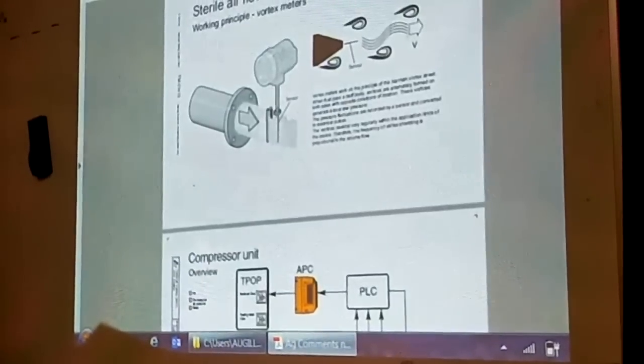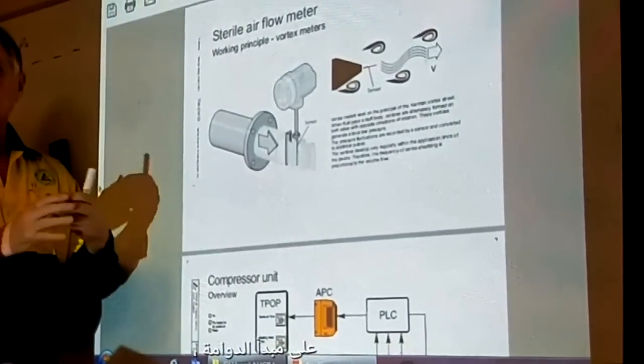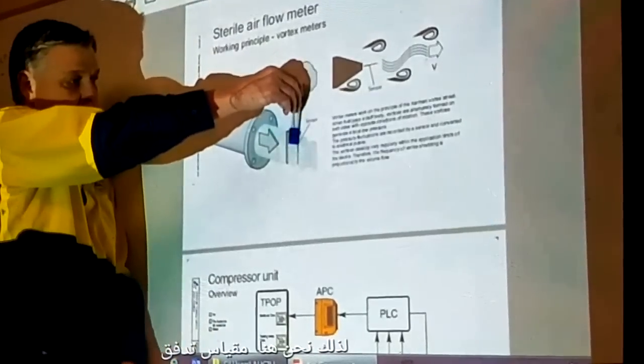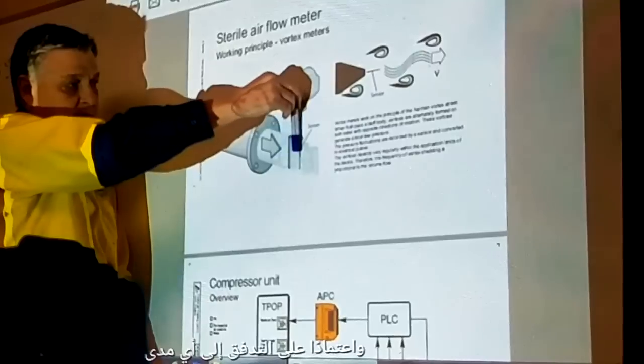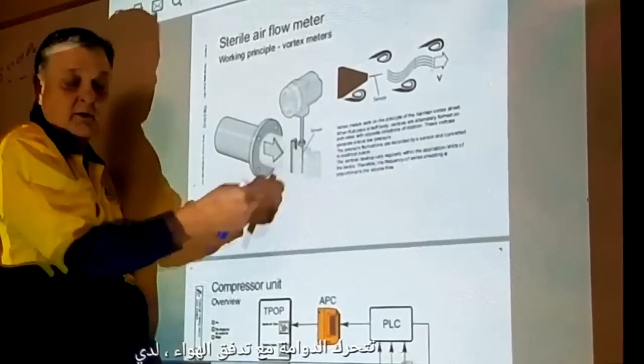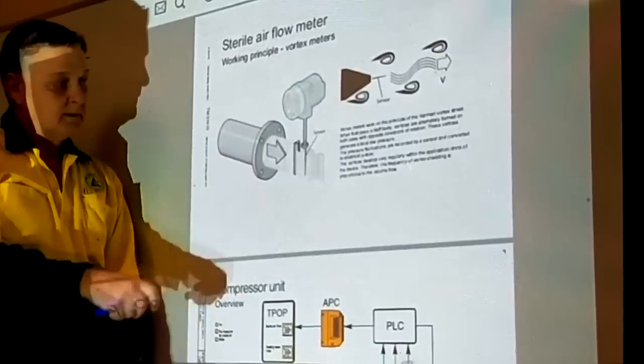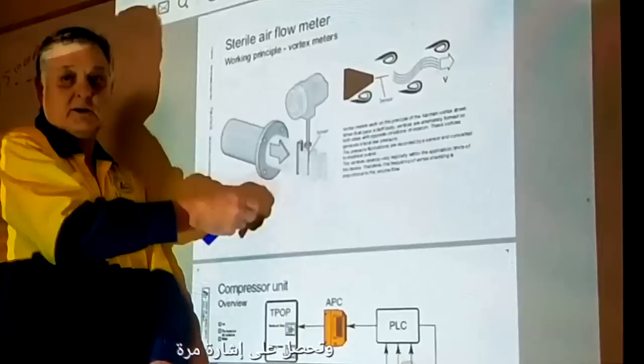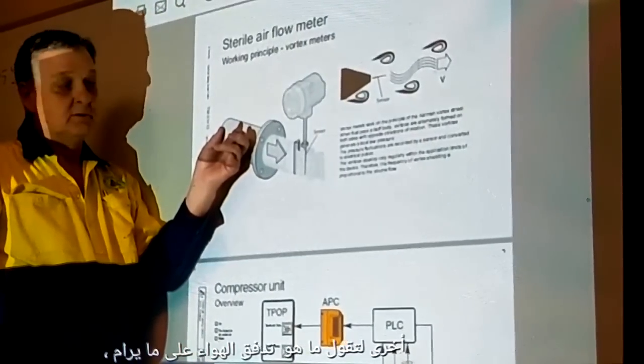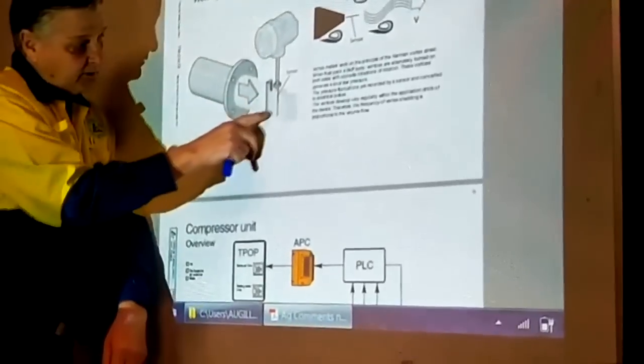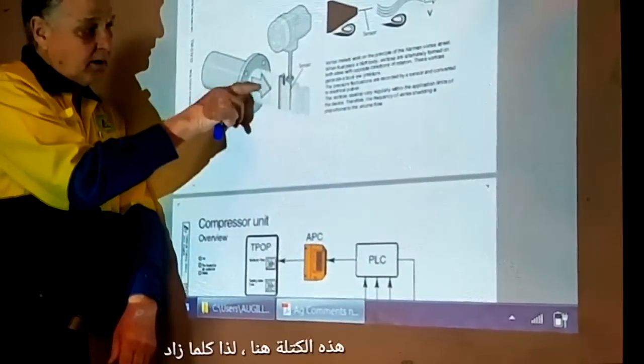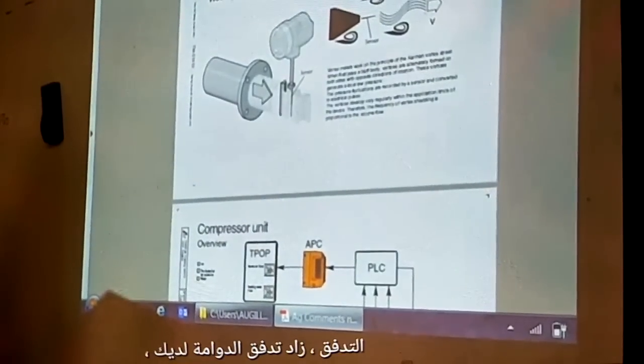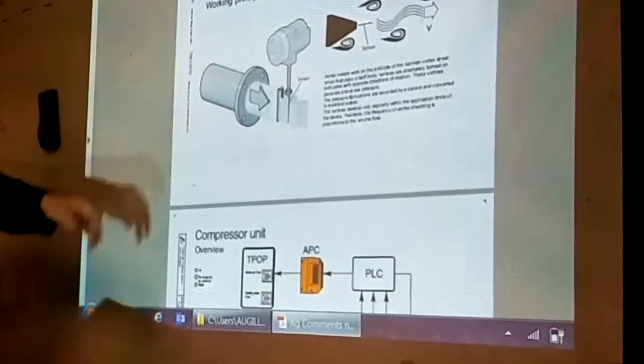Flow meter. It operates on a vortex principle. So here we have a flow meter, and depending on the flow, how much the vortex moves, gives the airflow. I've got a good video just to show you how. So depending on the flow, you get a signal back that says what the airflow is. It just creates vortexes around this block here. So the higher the flow, the more vortex flow you have. Okay. I have a good video. So that's the flow meter.